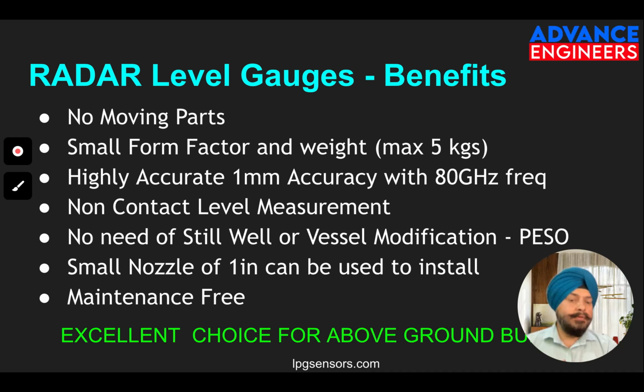You don't need any vessel modification, so no need of PESO approvals. That's the beauty - you just install a radar on top of the nozzle. The nozzle can be 1 inch also. We have radars which can be installed on half inch too, but for LPG we've seen minimum 1 or 1.5 inch nozzles are always available, so we recommend installing these radars on a 1 inch nozzle.